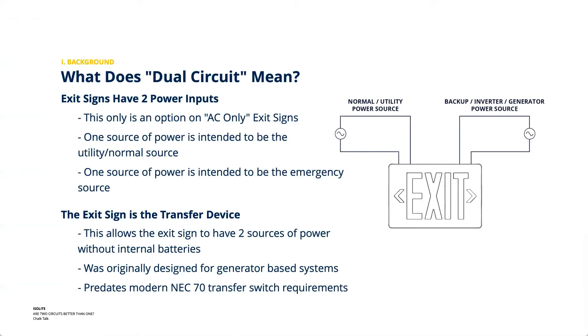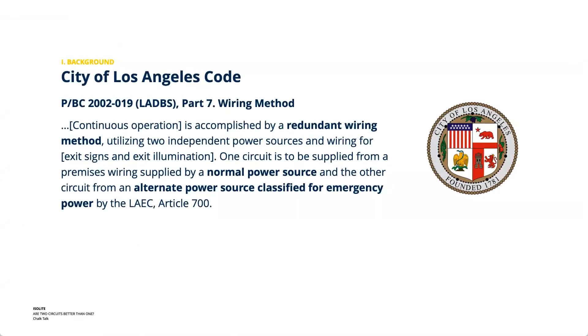This was originally designed for generator-based systems and predates modern electrical code. It came principally from the City of Los Angeles. What you see on screen is the old version of the code — early 2000s and earlier — which really nails it down: 'Continuous operation of emergency lighting is accomplished by redundant wiring methods utilizing two independent power sources and wiring for the exit signs.